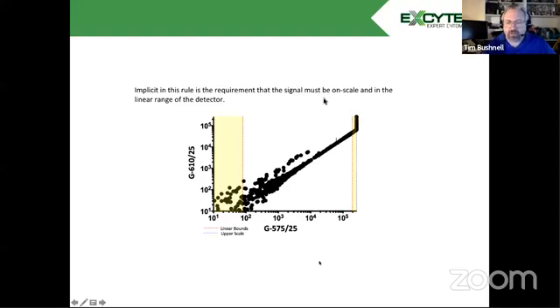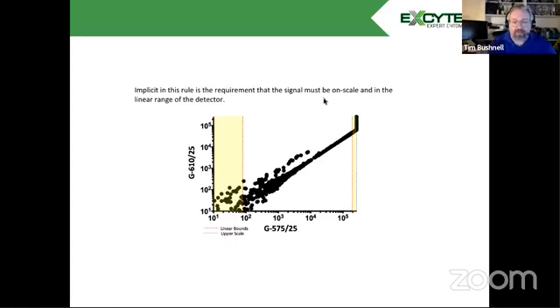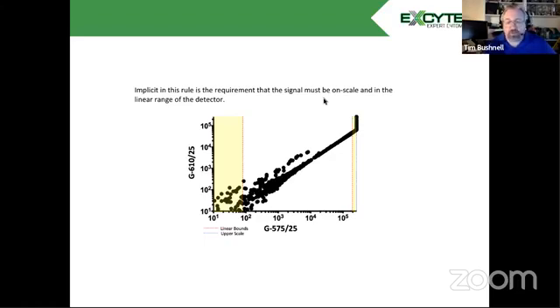You can get this information in a wide variety of ways. If you've got a BD instrument, CS&T will give this to you. You can calculate this using other beads as well to figure out what that dynamic range is, linear range. Eight peak beads, for example, is a great way to do that.